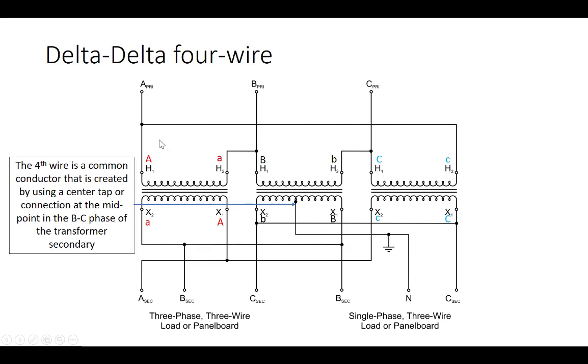When we look at how this is connected, on the primary we have a regular delta where the lines A, B, and C are connected to H1 of the single-phase windings, and the end of each winding is connected to the beginning of the next winding. End to beginning, end of B winding to beginning of C winding, end of C winding to beginning of A winding. On the secondary, we do the same thing.